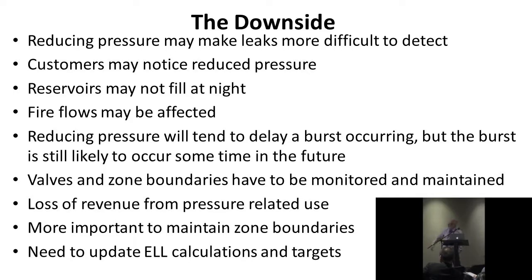Valves and zone boundaries have to be monitored and maintained. If you have a pressure managed area, controlled with shut valves, if those are opened, then all sorts of things happen. I can quote you examples where some leakage inspector opened some valves one night, suddenly high pressure is introduced into the adjacent area, and we have like 10, 15 bursts in that night. So you have to be very careful, particularly with boundaries.